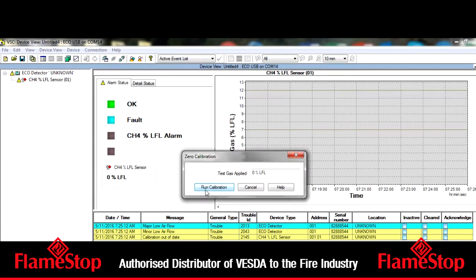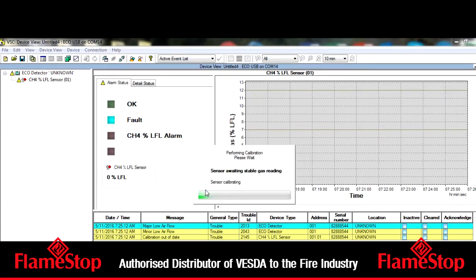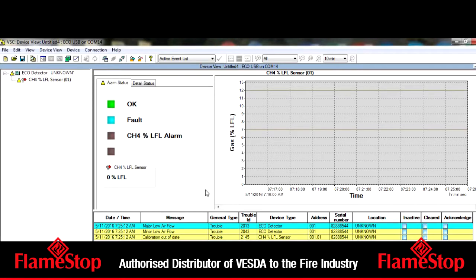Confirm the correct gas concentration, then run the calibration. The calibration process should take between 1 and 2 minutes to complete. The calibration is now complete and you are assured the detector is reading a true 0.